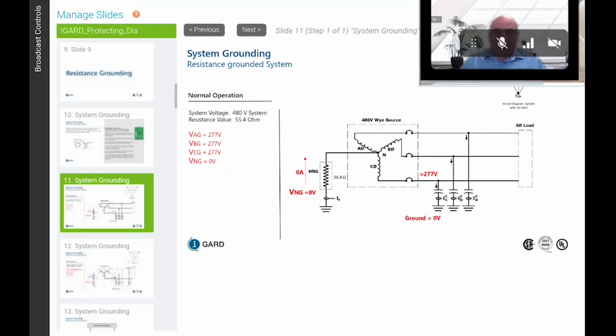So basically, if you have a system over here, this is a 480 volt secondary. You can see our vector relationship, A to neutral, B to neutral, C to neutral is 277 volts. Phase to phase, we're looking at 480 volts. If there's no ground fault on the system, there's no current flowing through the resistor. And we have 277 volts from A to ground, B to ground, C to ground, and neutral to ground. Neutral and ground are at the same potential because there's no current flowing through the resistor.